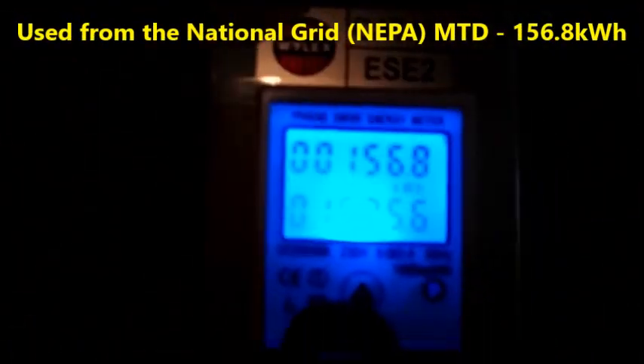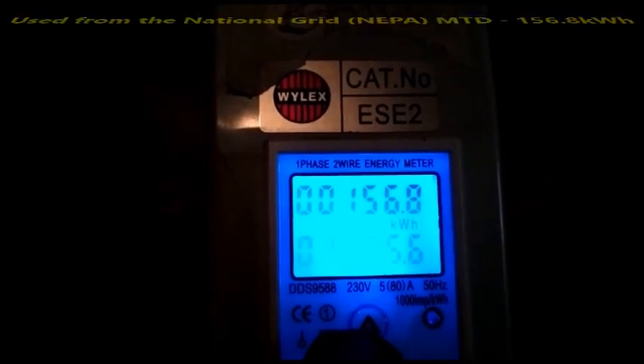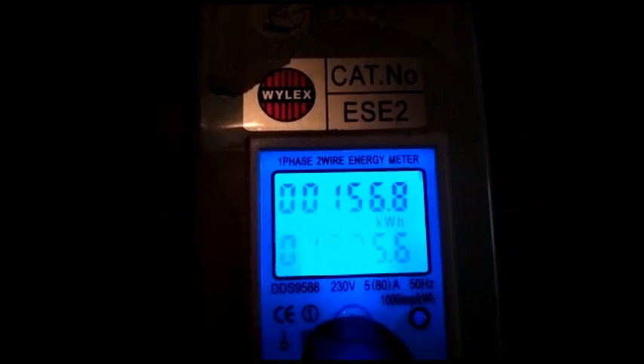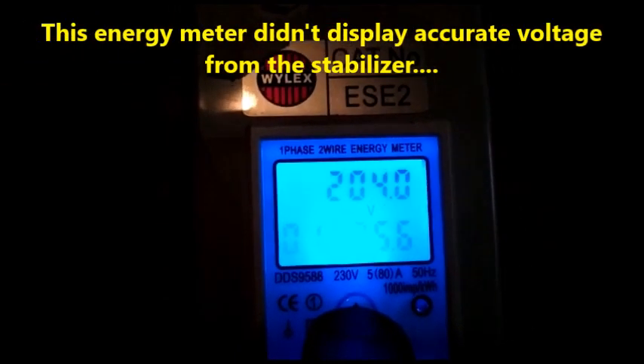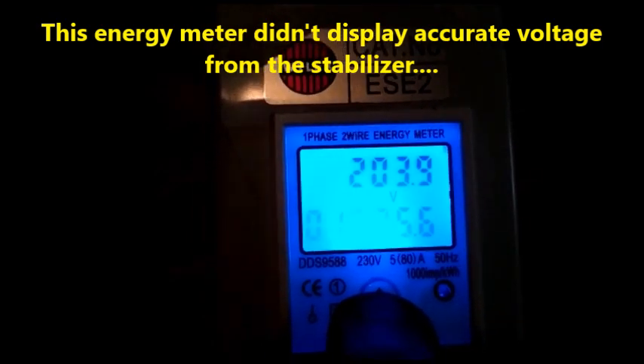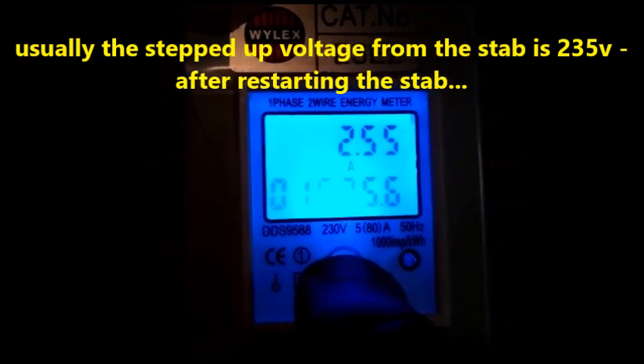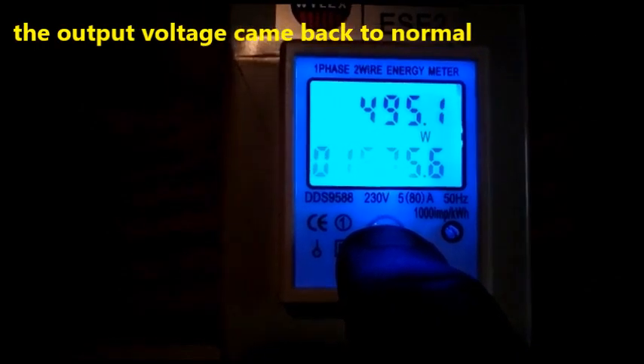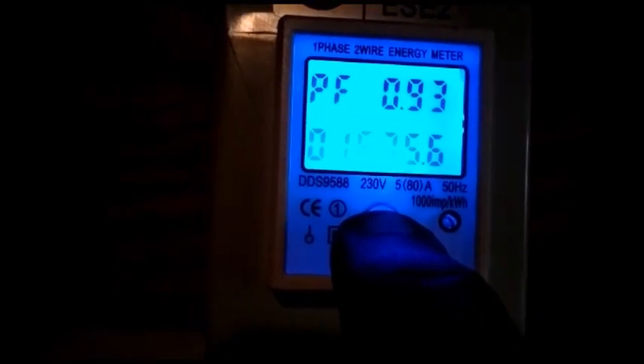Let's check the consumption for the month: 156.8 kWh used for the month. We are currently using 204.0 volts, 2.5 amps, 494.4 watts, and the frequency is 50 Hz with a power factor of 0.93.